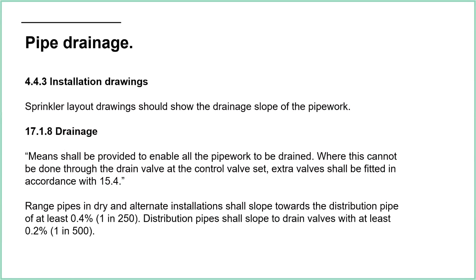But of course, that isn't always possible, and therefore we're going to have extra drainage points scattered around the building, scattered around the pipework to enable all pipework to be drained. But as I mentioned in, I think it was a previous sprinkler talk when I was talking about live tap, that's very difficult in practice to achieve. So we can use live tap to add extra drain points, but often it will just be left. There'll be a small pocket which doesn't fully drain, and that may just get ignored.